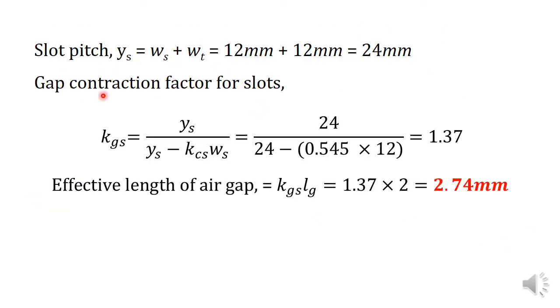The equation for gap contraction factor for slots, KGS, is equal to YS (slot pitch) divided by (YS minus KCS times WS). Here YS equals WS plus WT, which is 12 plus 12 equal to 24 mm. Substituting the values: 24 divided by (24 minus 0.545 times 12), KGS is equal to 1.37.